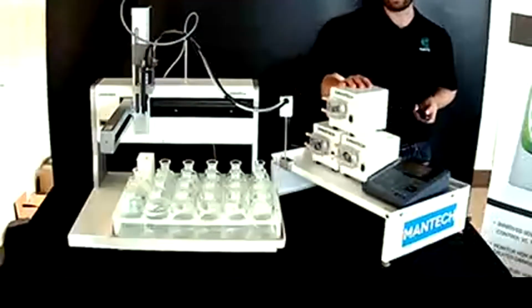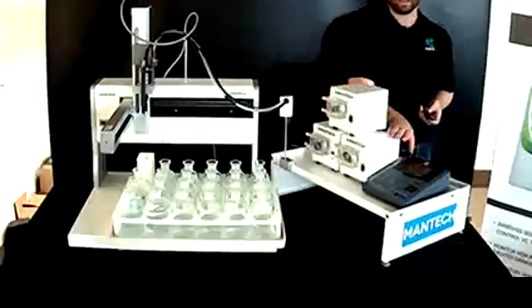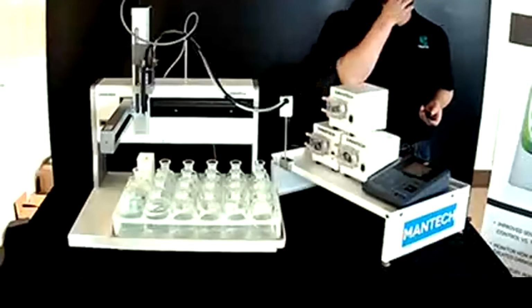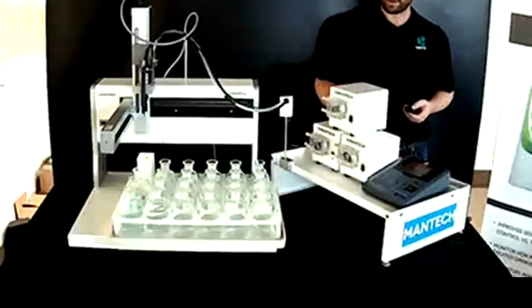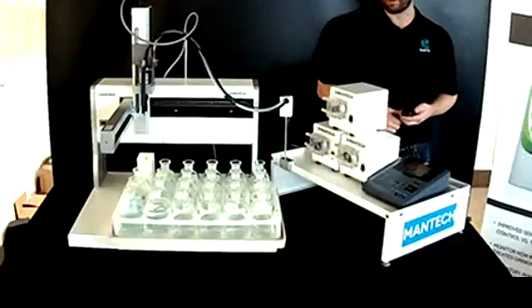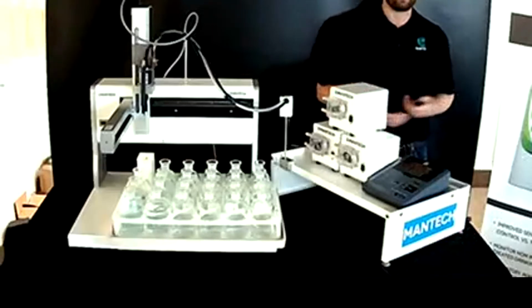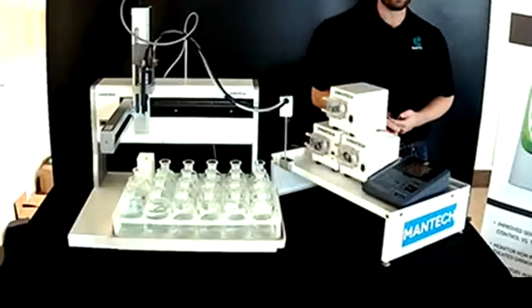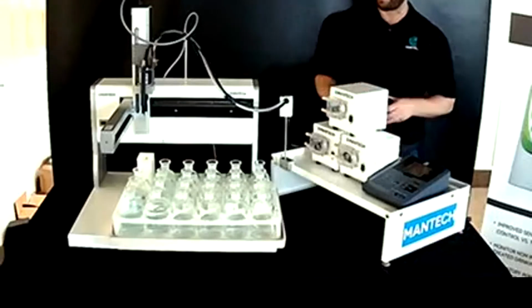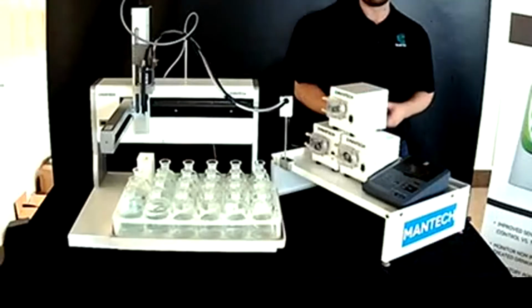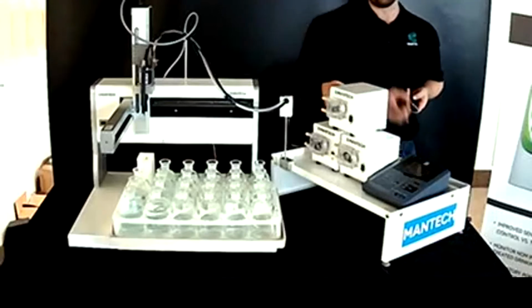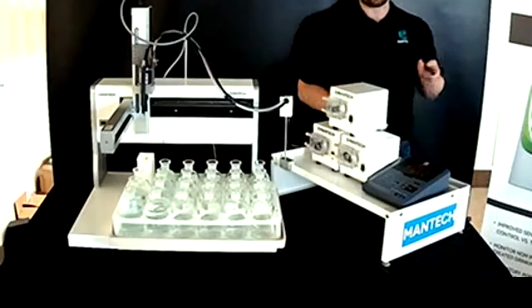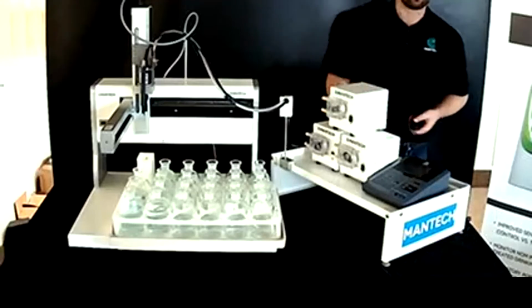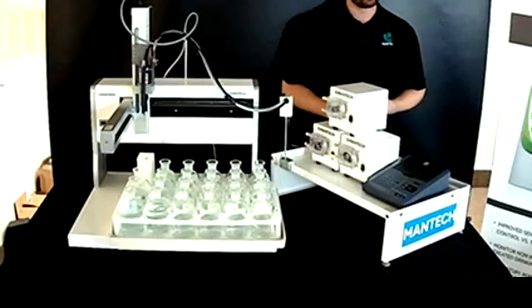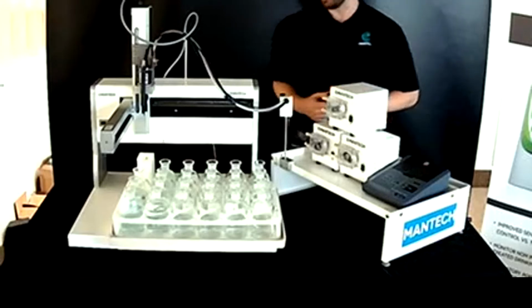So that would be a dilution pump, seed pump, and inhibitor pump if you're doing carbonaceous BOD. And we can also add on other pumps if you wanted to. We have added additional pumps and even more precise burette modules, depending on customer needs. But this is a very standard setup right here, automatically adding those 3 reagents. You have your DO meter right here, and that can be hooked up to 1, 2, or 3 different DO probes, both membrane and optical variety.